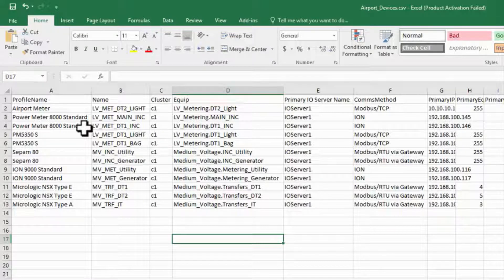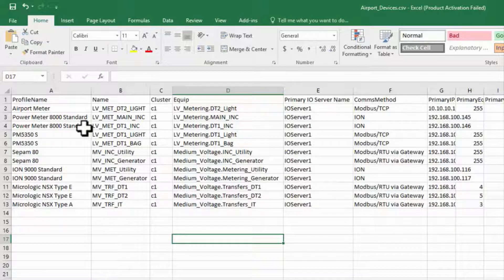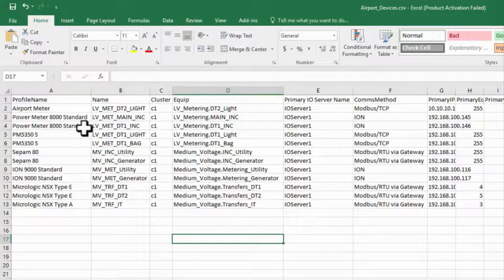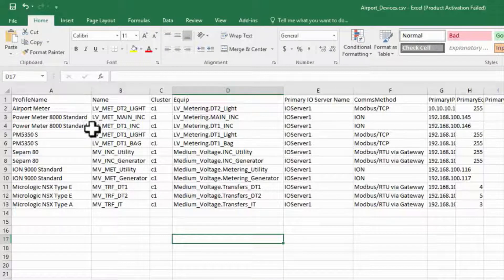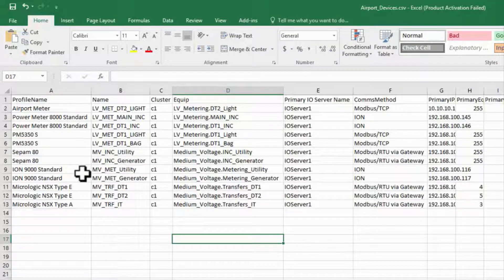Secondly, having a capable meter may not be enough. The meter must be configured to capture waveforms on appropriate events. For ION meters specifically, this means setting a nominal voltage, but other meter lines will have similar requirements.